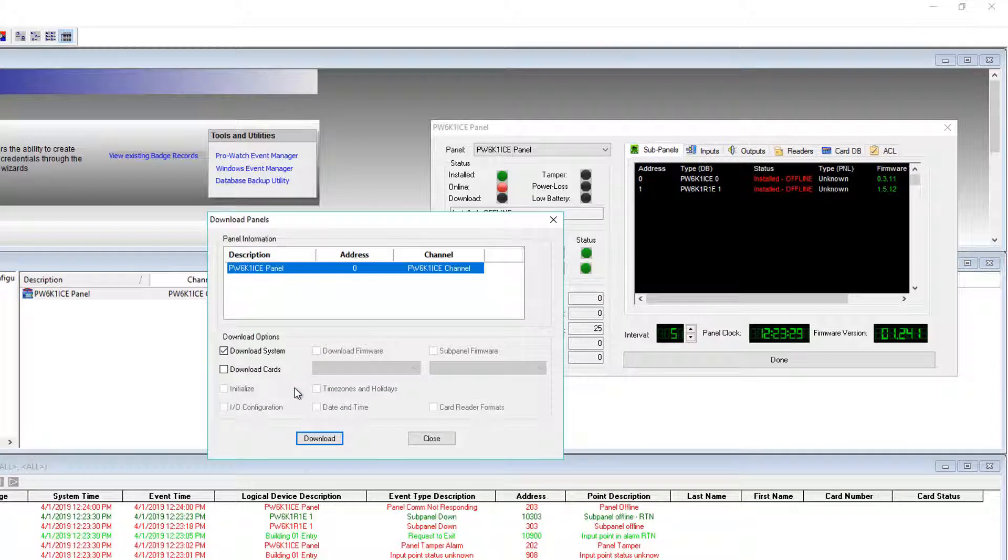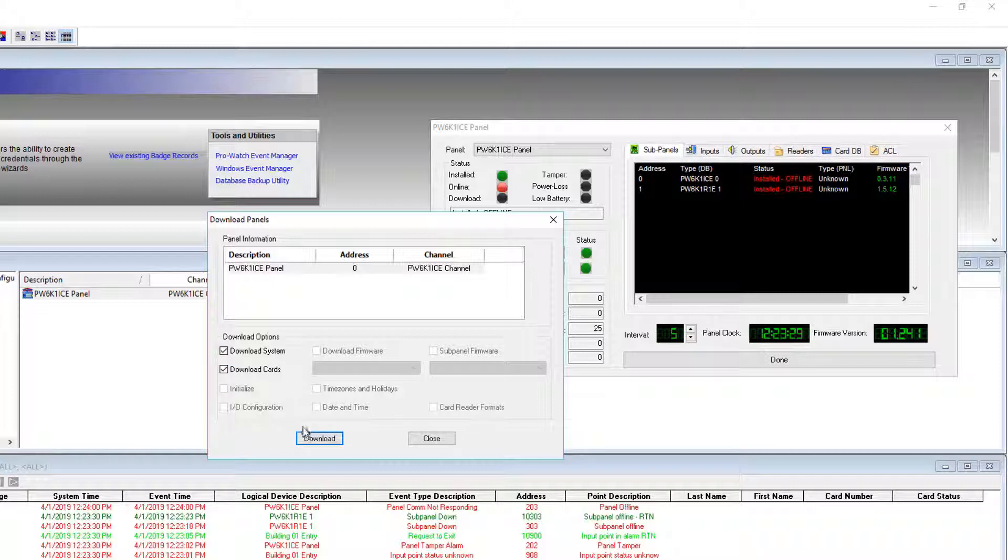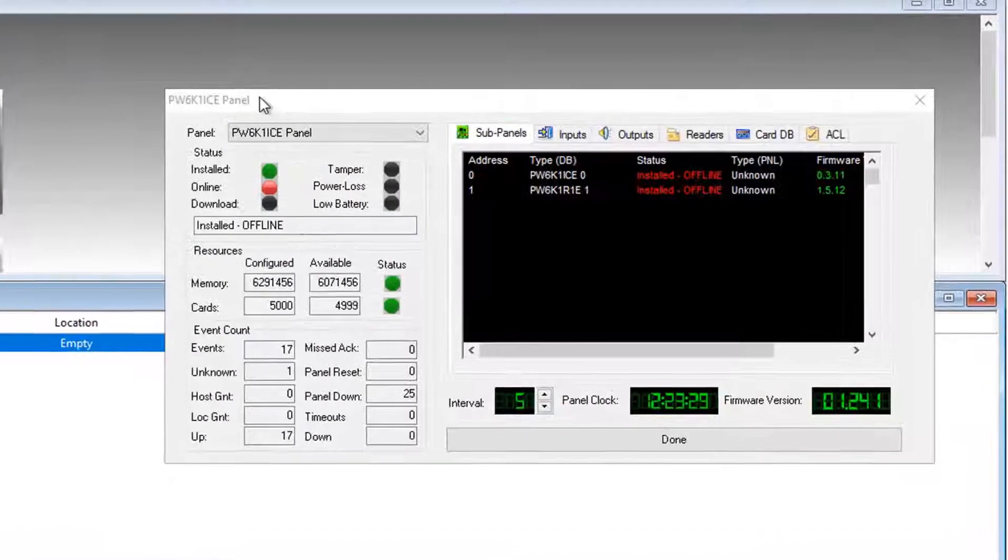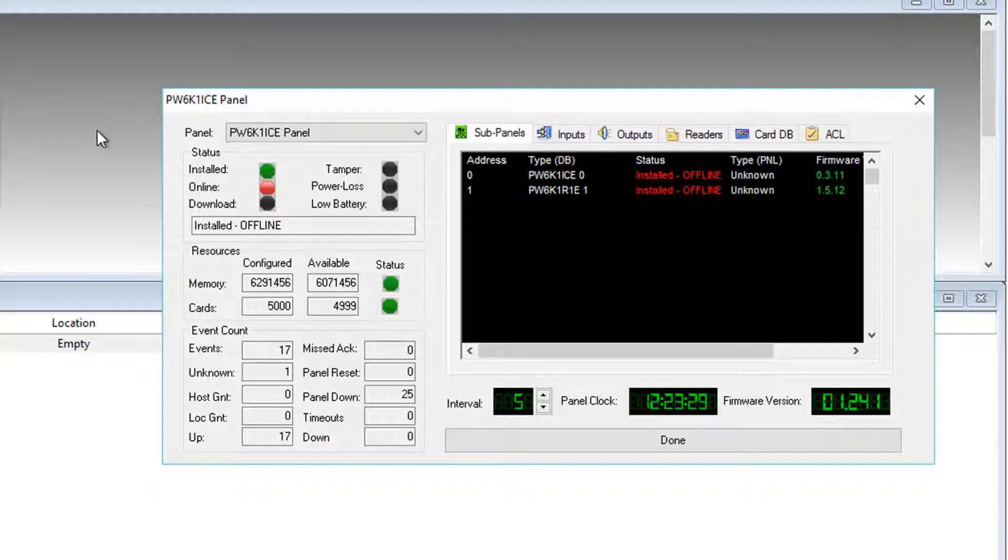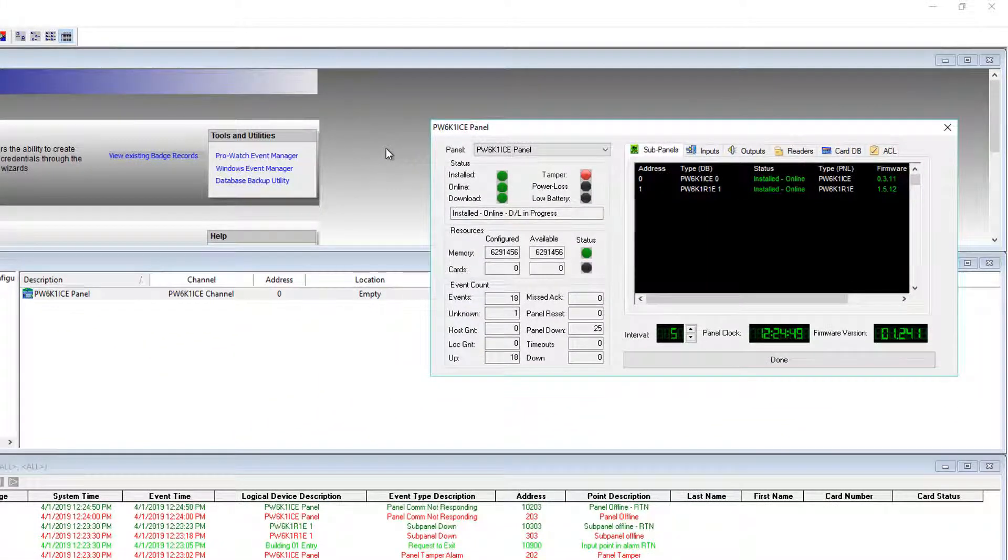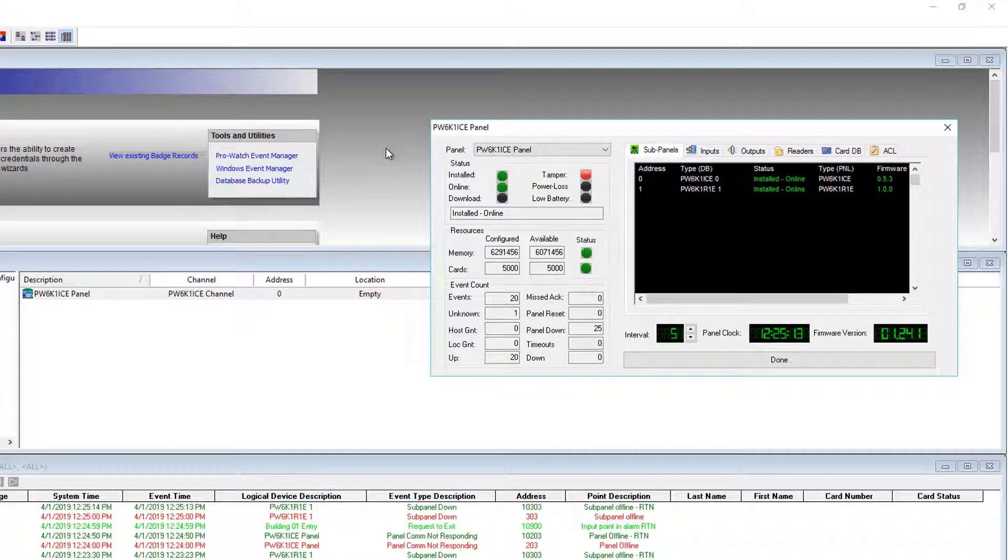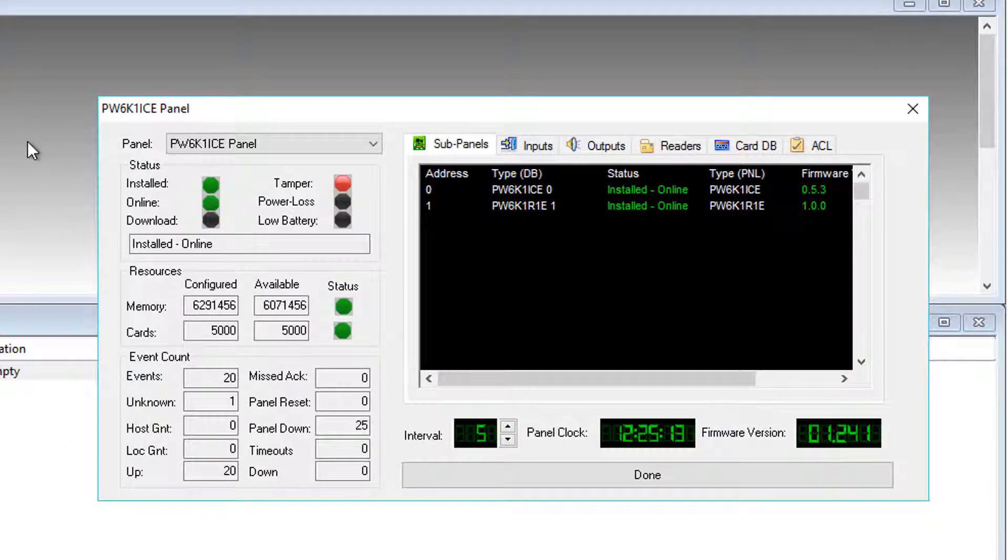We can again right-click Check Download, and leave Download System checked, and add download cards to that. Click Download. Step three is quick. We just follow up the initialize on step two with a quick download of System and Cards. And we'll see here in panel status that once complete, the controller will be back online, and we'll take a download of System and Cards.